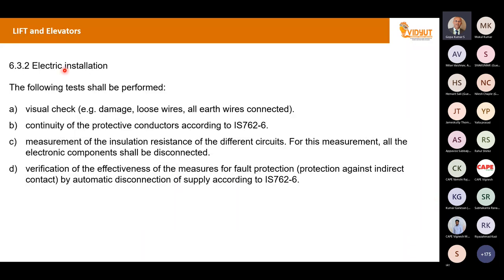That is point number one. Also, verification in clause 6.3.2 covers electrical installation visual check and continuity of protective conductors, meaning the resistance of the earth connection is intact so protective devices can operate. Then measurement of insulation resistance, and finally verification of the effectiveness of fault protection measures like automatic disconnection — that is RCD testing or MCB fault loop impedance testing. All these are included in the upcoming standard.